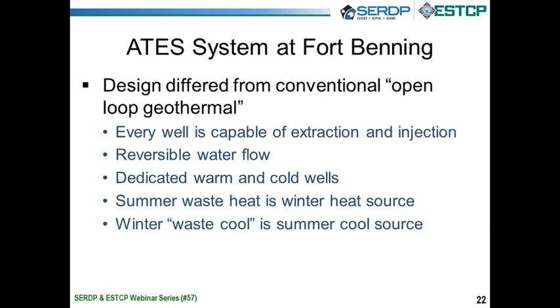The ATES system that was installed at Fort Benning differs from conventional open-loop geothermal in that every well is capable of extraction and injection. So each well can pull water out of the ground or put water back down in the ground. And the flow of the water is reversible. And so we end up with dedicated warm wells and cold wells. So if we're passing water through the building in the summer, we're creating warm water. So that waste heat goes down into a warm well and is used as our winter heat source.